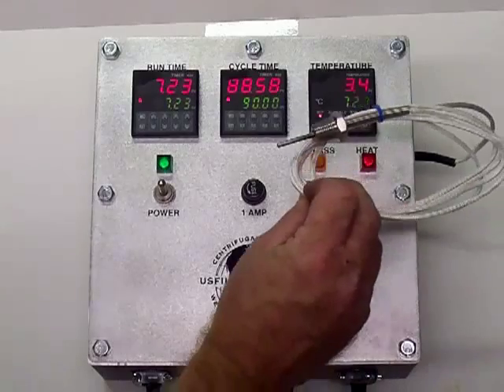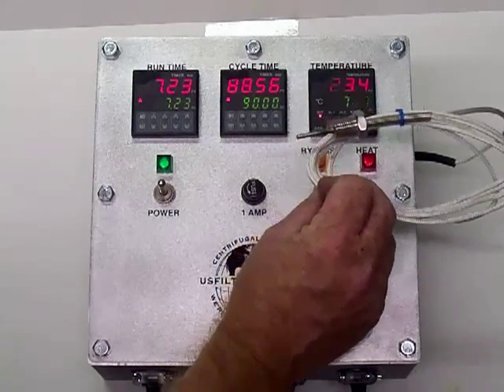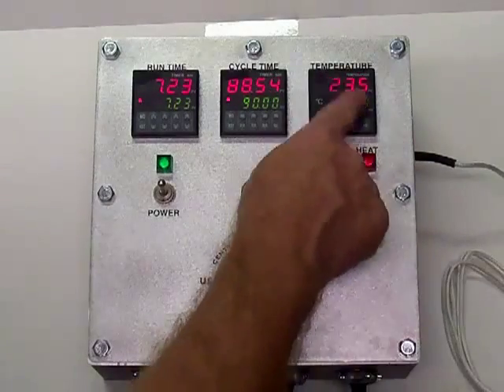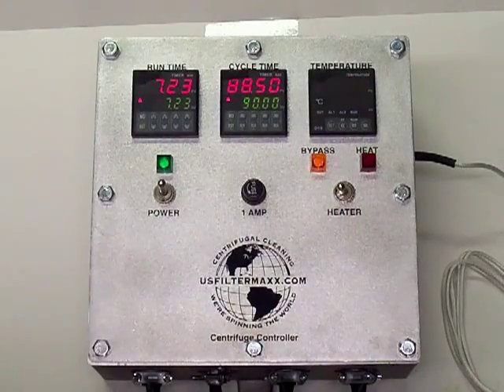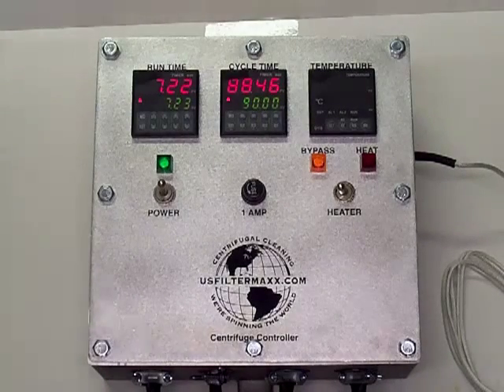Right here in the room it's 23.4 degrees. You have a thermocouple probe that goes into your heater, and that is what controls your set temperature. You can always bypass the heater — turn it off like that. Next, we'll look at the US FilterMaxx variable speed centrifuge controller.